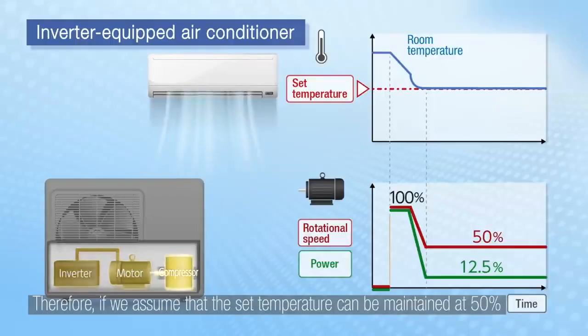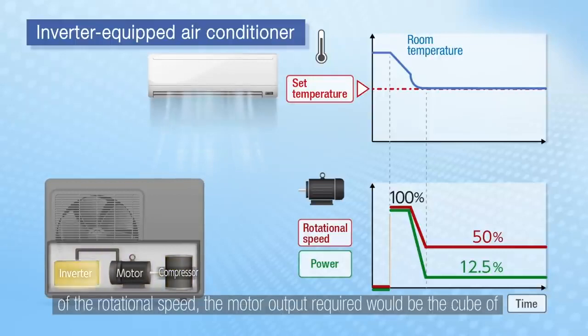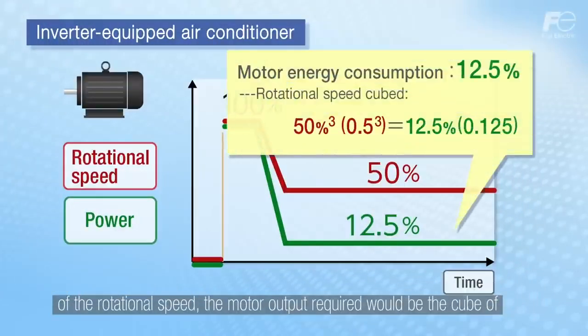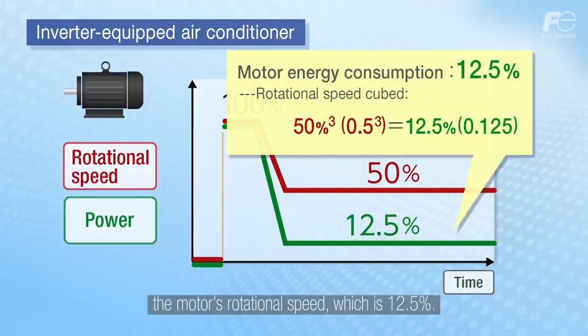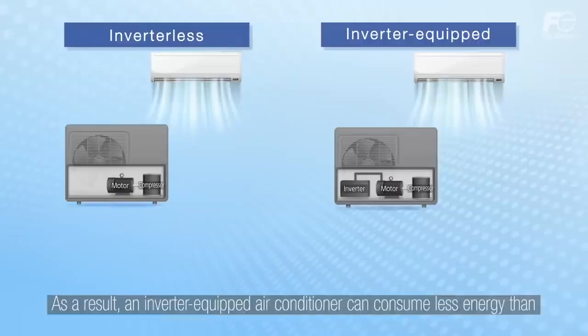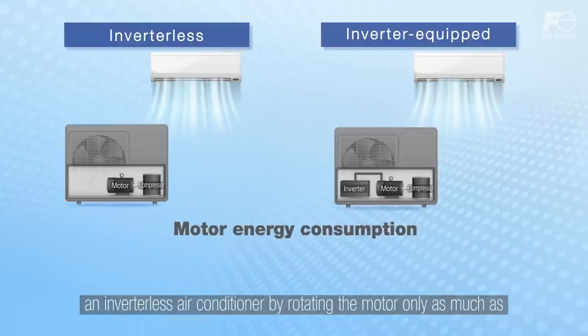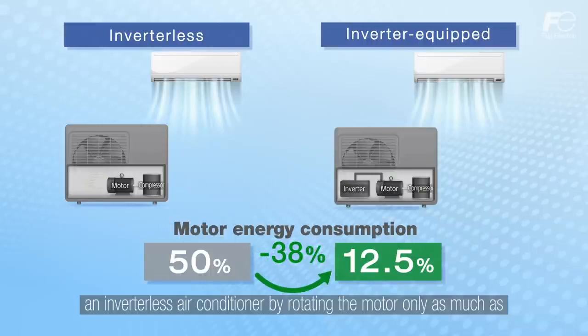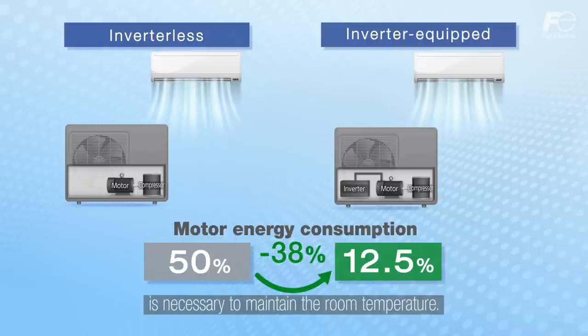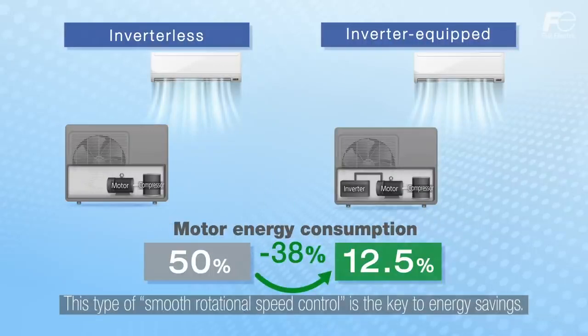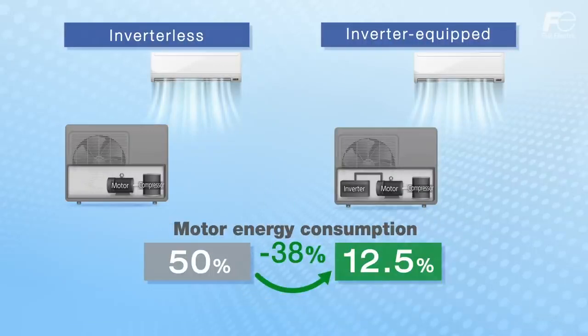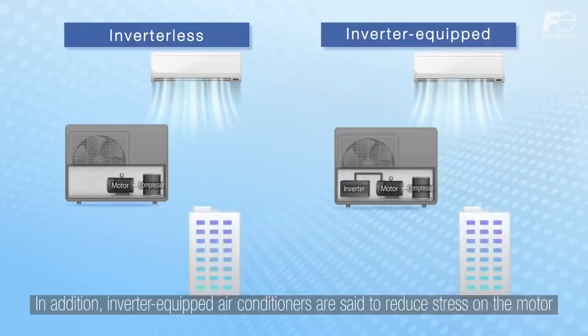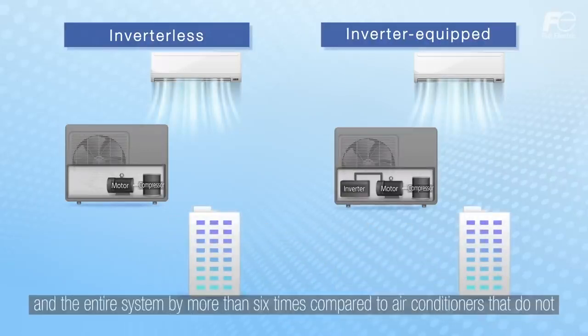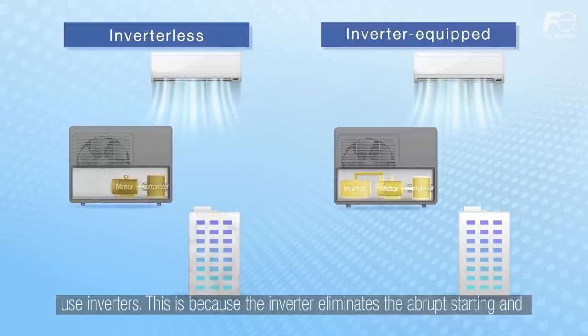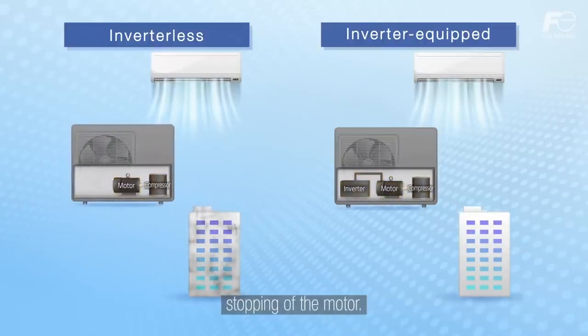Therefore, if we assume that the set temperature can be maintained at 50% of the rotational speed, the motor output required would be the cube of the motor's rotational speed, which is 12.5%. As a result, an inverter-equipped air conditioner can consume less energy than an inverterless air conditioner by rotating the motor only as much as is necessary to maintain the room temperature. This type of smooth rotational speed control is the key to energy savings. In addition, inverter-equipped air conditioners are said to reduce stress on the motor and the entire system by more than 6 times compared to air conditioners that do not use inverters. This is because the inverter eliminates the abrupt starting and stopping of the motor.